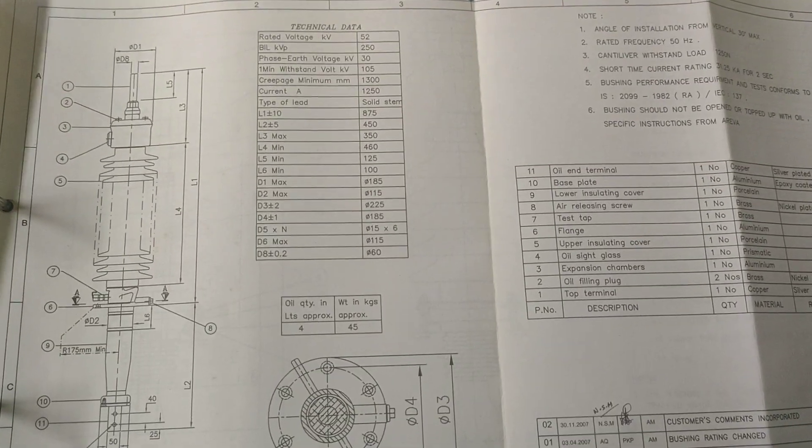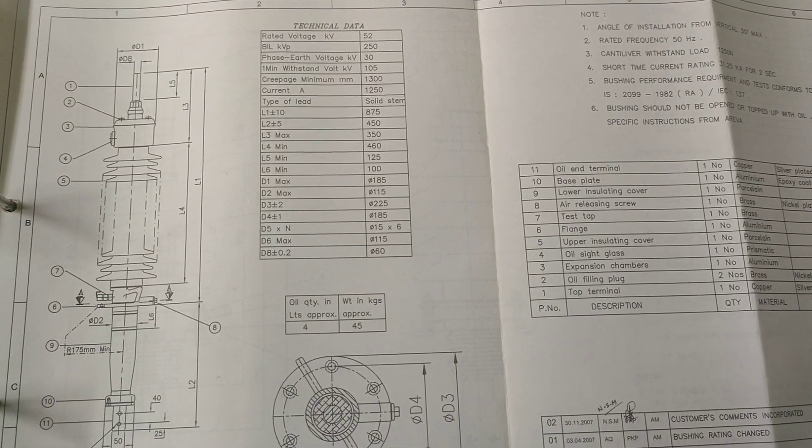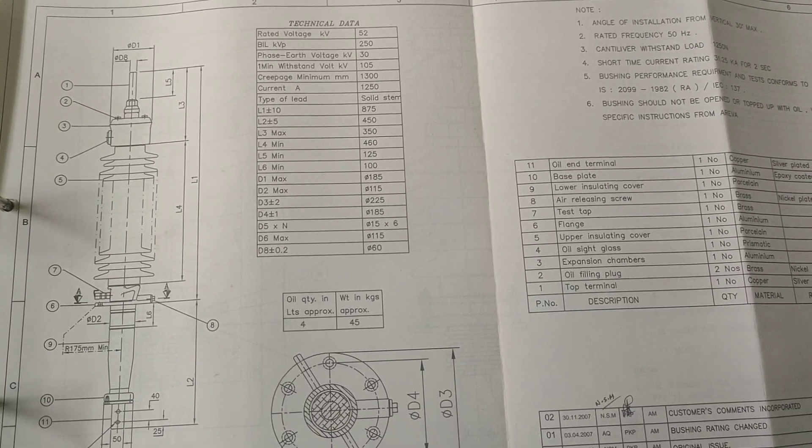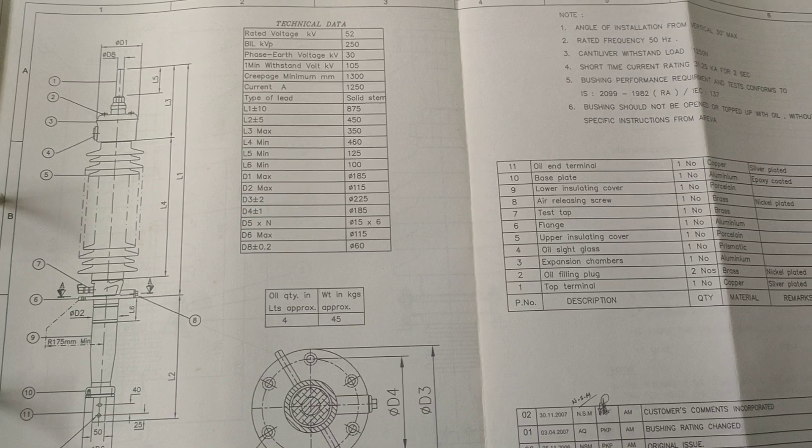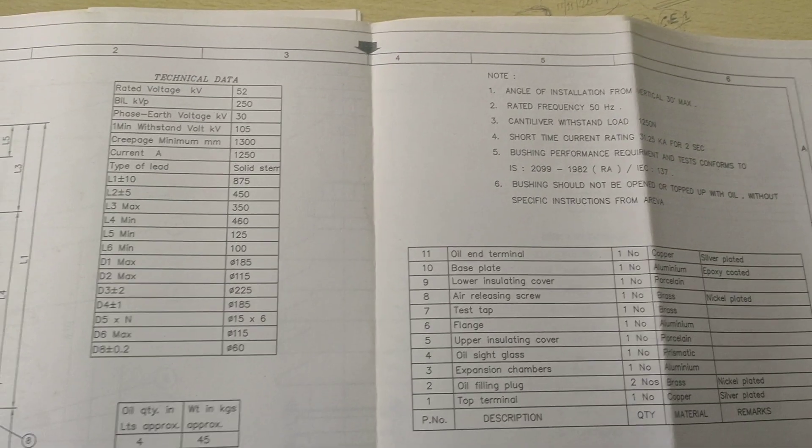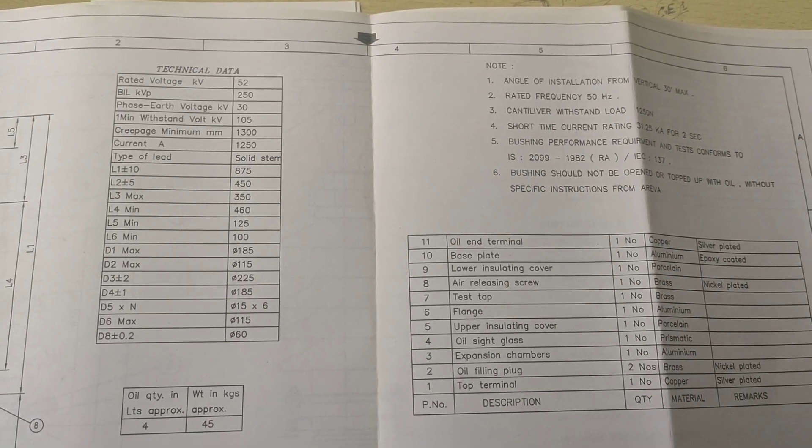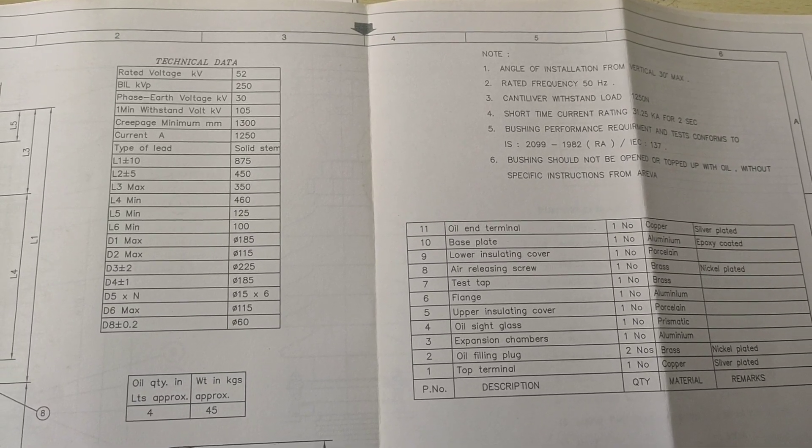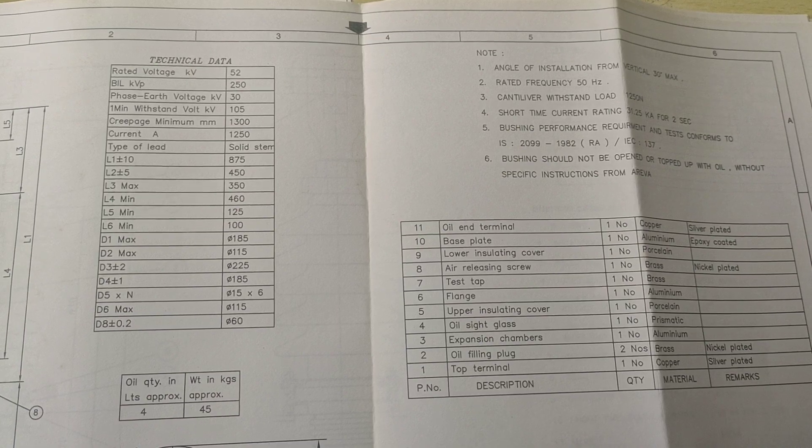This is the picture of the LV type bushing, and the specifications are given here. The rated voltage is 52 kV, basic insulation level 250. All the details are given here. The creepage distance is given here. This is the short circuit current rating, 31.25 kiloampere for two seconds, and the current rating is 1250 ampere LV tertiary bushing.